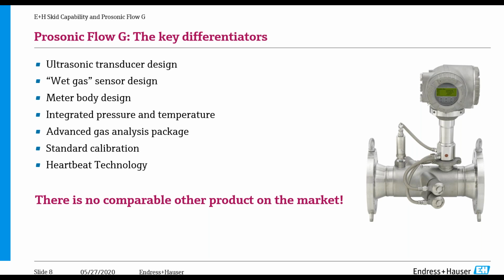This is not necessarily typical with other manufacturers, but for us, every single meter is flow calibrated. So it does go on a flow calibration rig. And we have our Heartbeat Technology monitoring the system and the health of the meter.